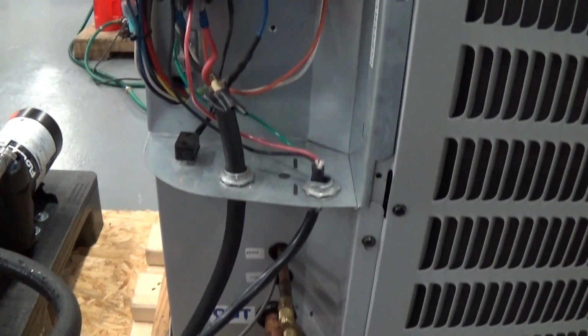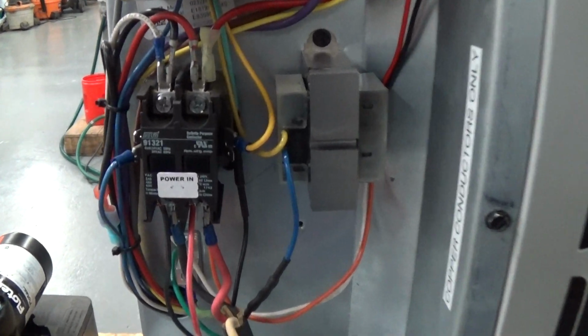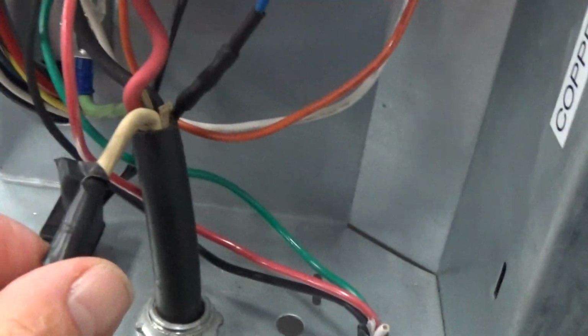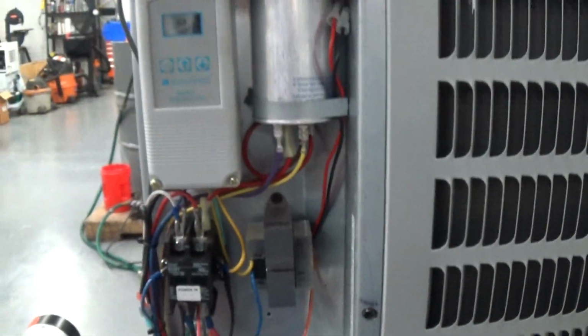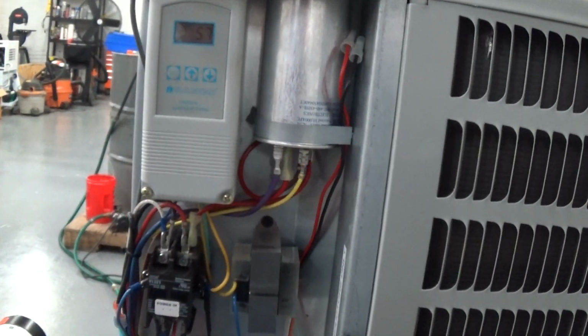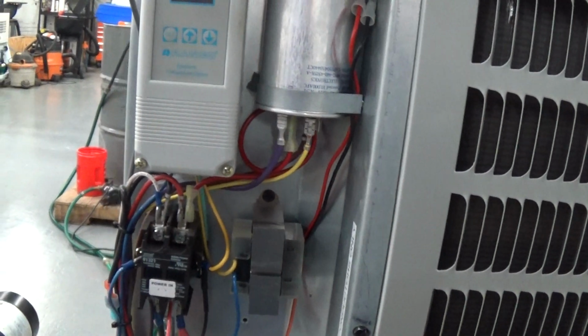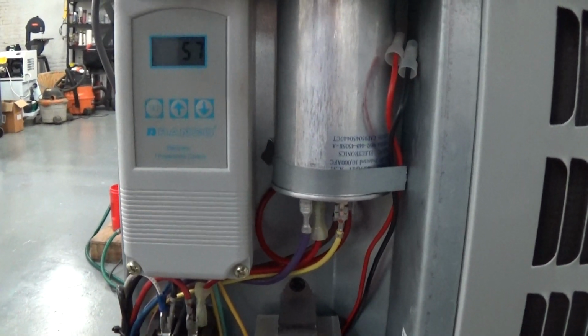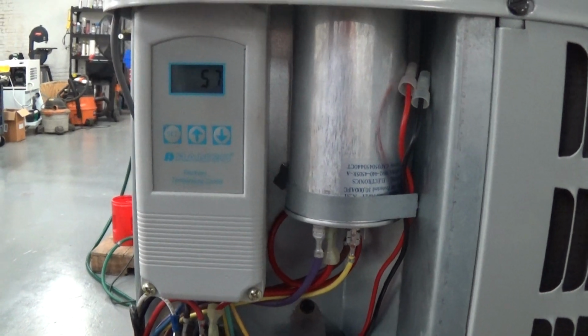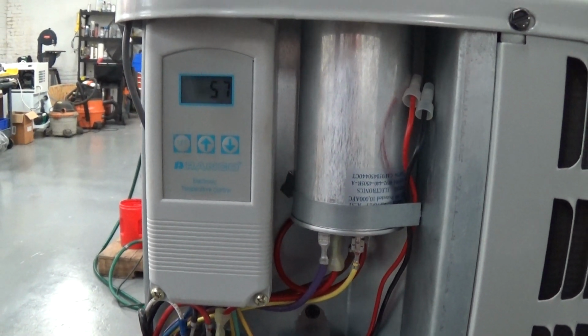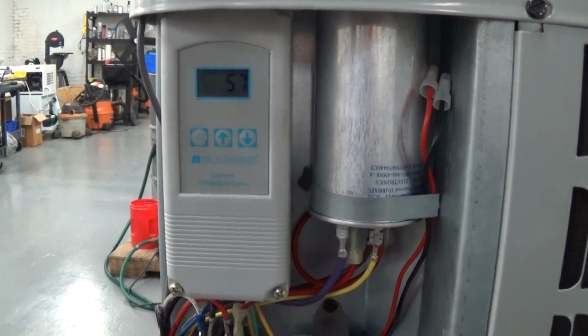So you just bring your main power here in the outdoor section. Right, it says power in. It's pretty simple because it's single phase power. You got a red, a black. This is just our power cord. It's just capped off, and then your ground. The simple Ranco controller. What you want to do is you always want to get away with the highest differential that you can. I'd like to see you start out with 4 or 5 degrees. 2 degrees is probably too tight. That'll induce short cycling with the chiller.